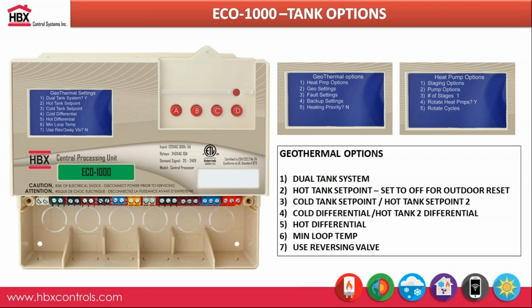In terms of your set points off your hot and cold tank, with the 1000, you can have a target set point all the time, or you can go off of outdoor reset just for the heating on the 1000. For a cold tank, it can only be a set point. We don't have that outdoor reset option for the cooling on the 1000. If you're just using these tanks, you're not utilizing a cold tank, you have the option of actually controlling two hot tanks with the 1000.